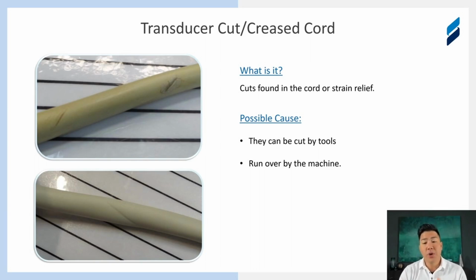And the reason we want to call this to your attention is because while the superficial damage may not puncture all the way through the protective layer of the cord, it's all the micro wires inside that rubber covering. The wires are 42 gauge to 44 gauge coaxial wires, and there's over 100 of them in there. So with that kind of cut, it could actually possibly cut the wires on the inside, giving you a ton of image quality issues, likely dropouts, at least some noise in color or CW.